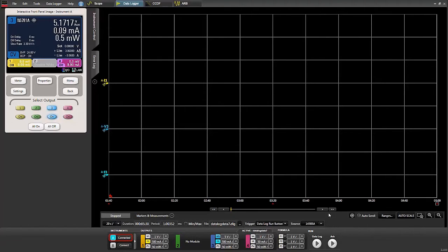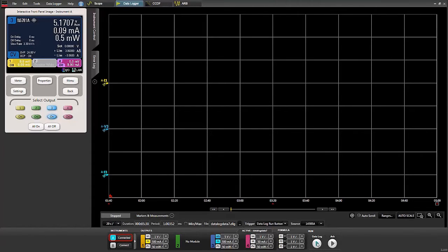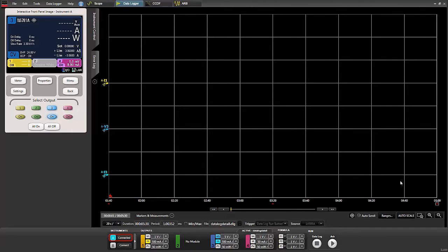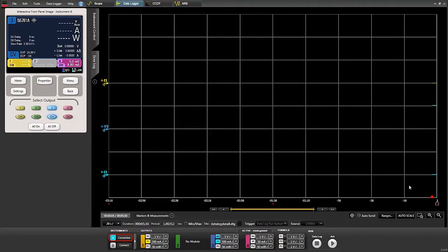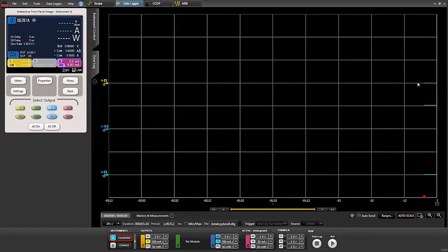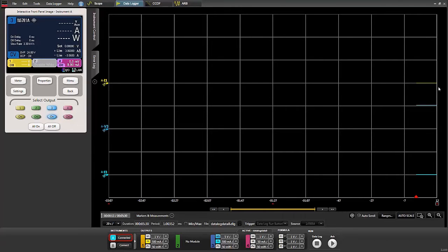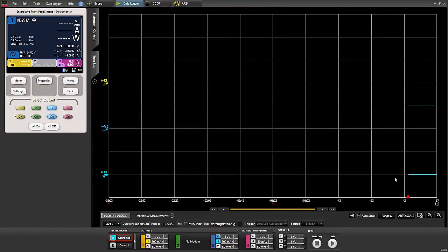I'll go down to the data logger start button at the bottom. I'll click on that and we'll start to see our strip chart of measurements. Currently you'll see the current on channel one as zero because the output is off at the moment, and the current on channel three is also zero because I have not plugged in the charger.